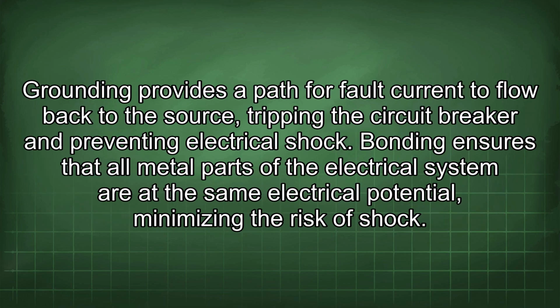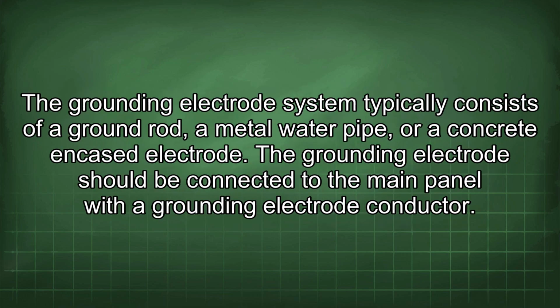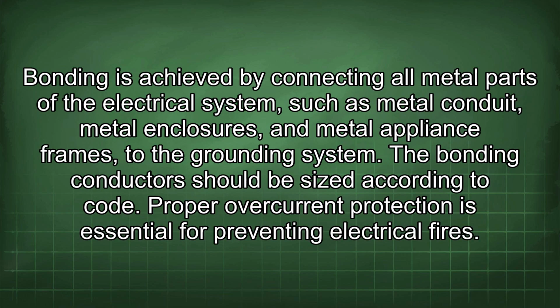Grounding provides a path for fault current to flow back to the source, tripping the circuit breaker and preventing electrical shock. Bonding ensures that all metal parts of the electrical system are at the same electrical potential, minimizing the risk of shock. The grounding electrode system typically consists of a ground rod, a metal water pipe, or a concrete encased electrode. The grounding electrode should be connected to the main panel with a grounding electrode conductor. Bonding is achieved by connecting all metal parts of the electrical system, such as metal conduit, metal enclosures, and metal appliance frames, to the grounding system. The bonding conductors should be sized according to code.